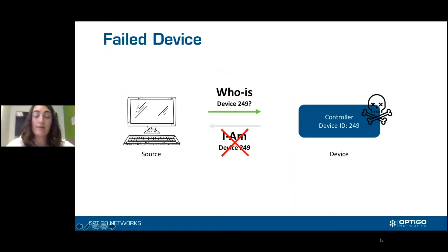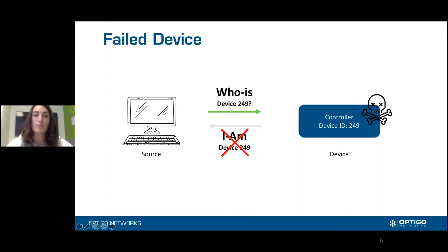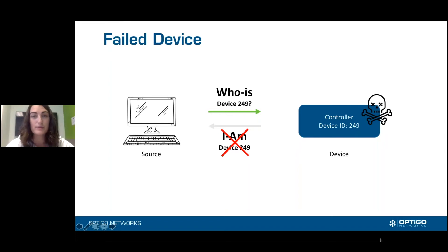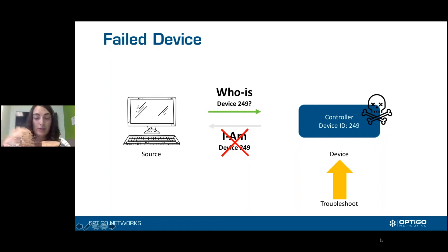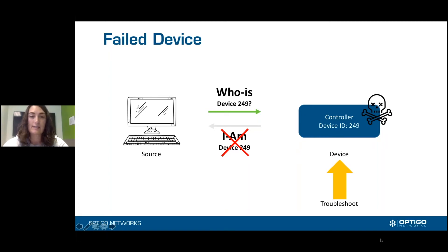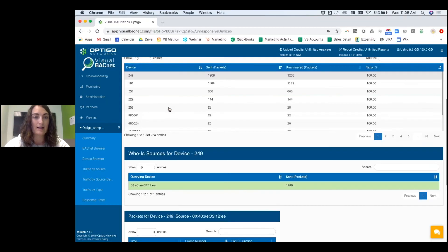Back in the PowerPoint — if that device ID should be on the network, it's in your list, it's assigned, and it's potentially talked in the past — and in Visual BACnet Site Monitoring you'll be able to see it has been sending messages for a long time and then stopped — in that scenario you may have a failed device. This is something many of you are probably familiar with. There are many different reasons it could have happened. In this case, you want to go troubleshoot that device: make sure it's plugged in, check for misconfiguration or an actual hardware problem.